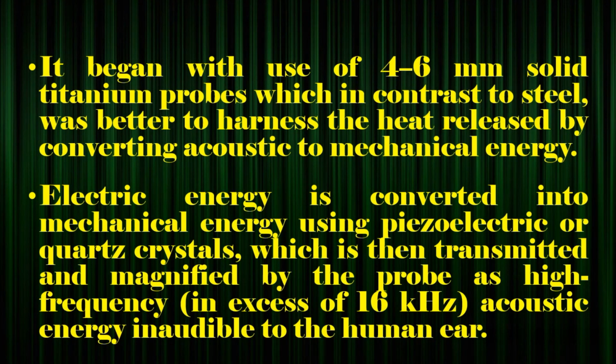It began with use of 4 to 6 mm solid titanium probes, which, in contrast to steel, were better to harness the heat released by converting acoustic to mechanical energy. Electric energy is converted into mechanical energy using piezoelectric or quartz crystals, which is then transmitted and magnified by the probe as high frequency, in excess of 16 kHz, acoustic energy inaudible to the human ear.